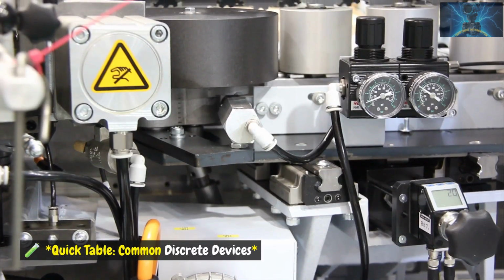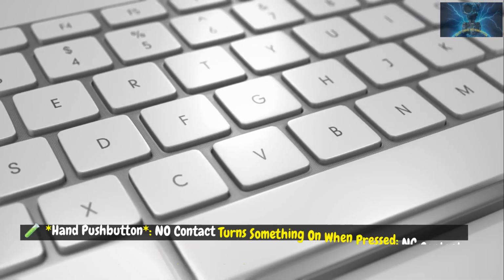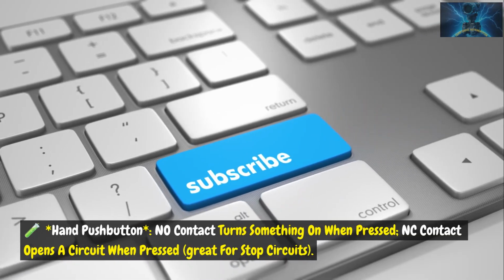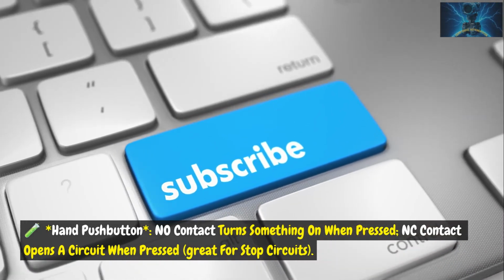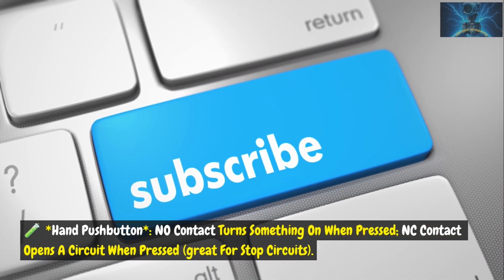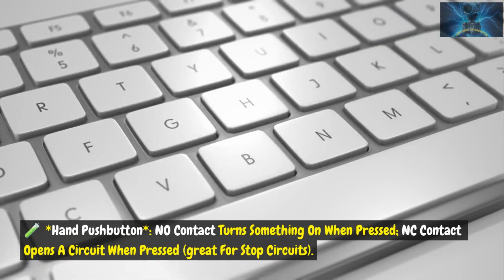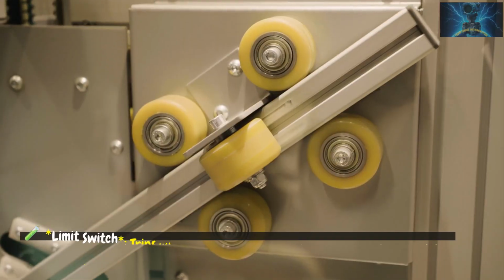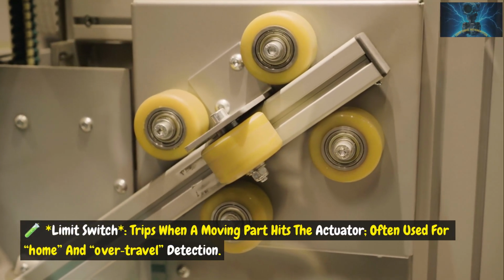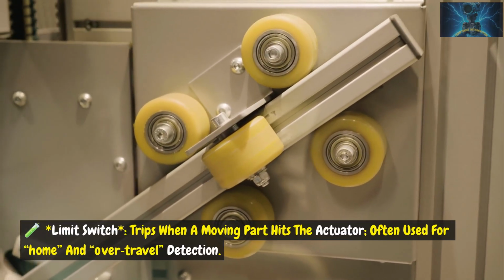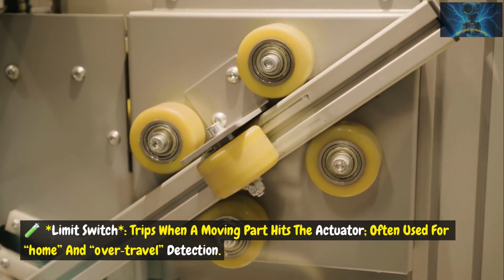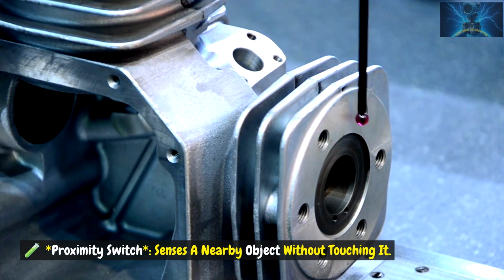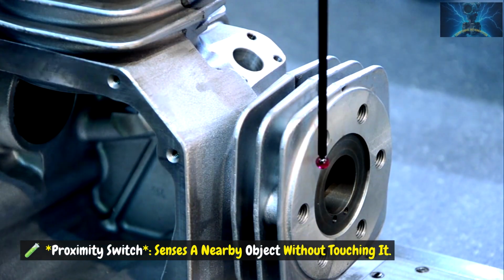Quick table: common discrete devices. Hand push button: NO contact turns something on when pressed. NC contact opens a circuit when pressed. Great for stop circuits. Limit switch: trips when a moving part hits the actuator, often used for home and over-travel detection. Proximity switch: senses a nearby object without touching it.